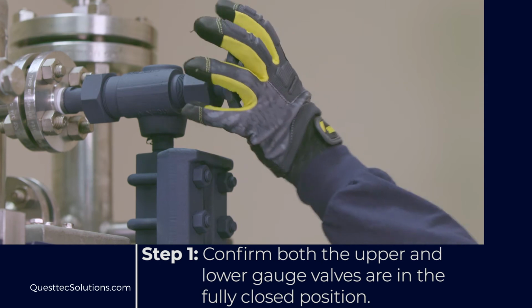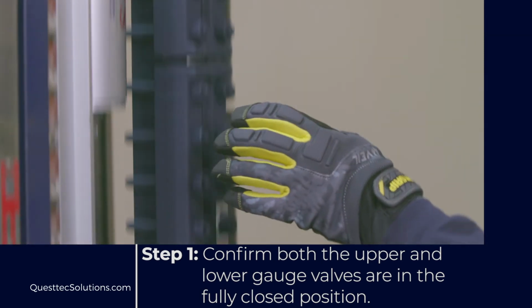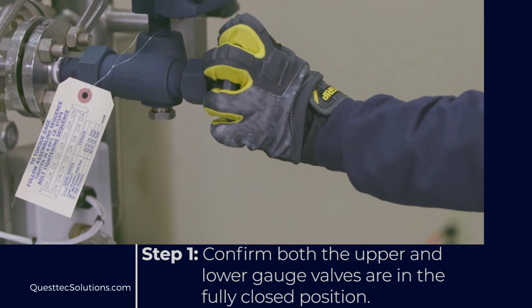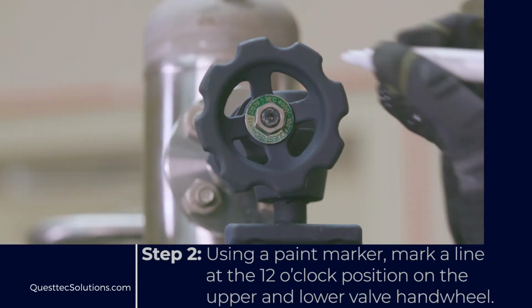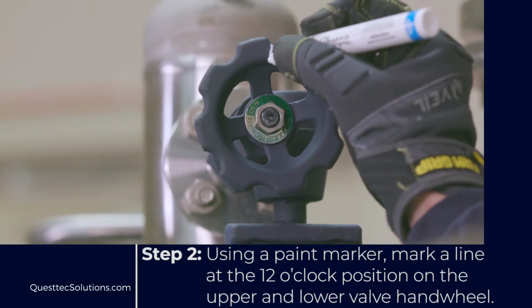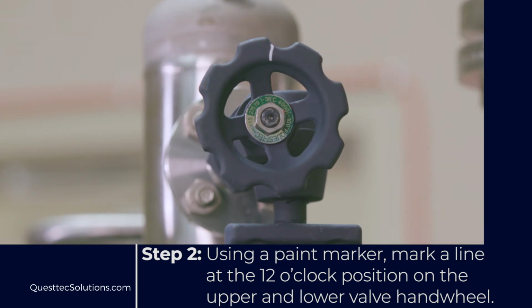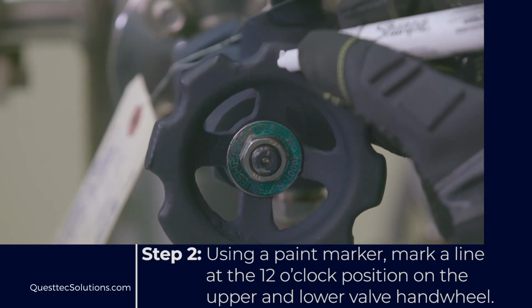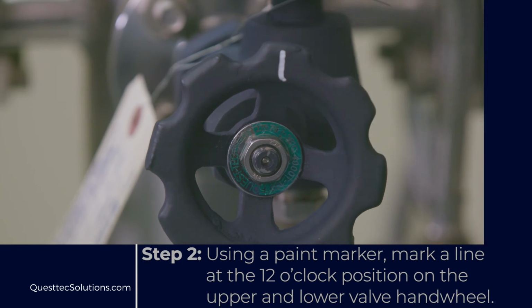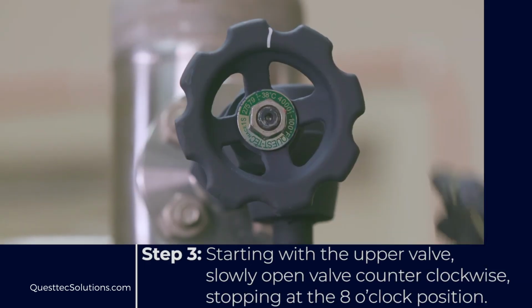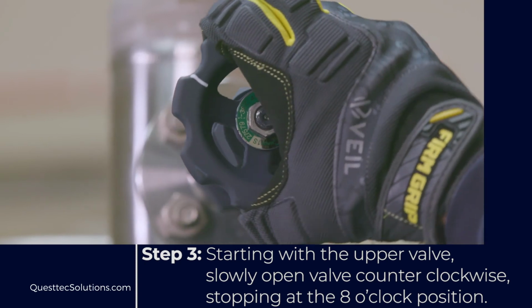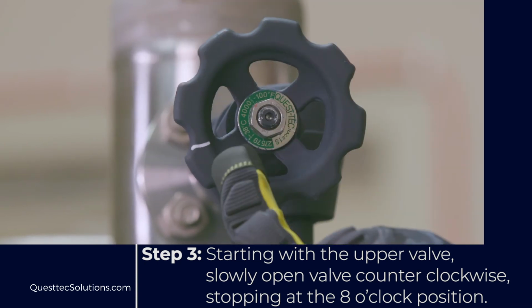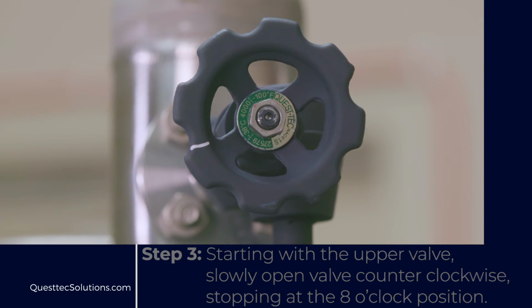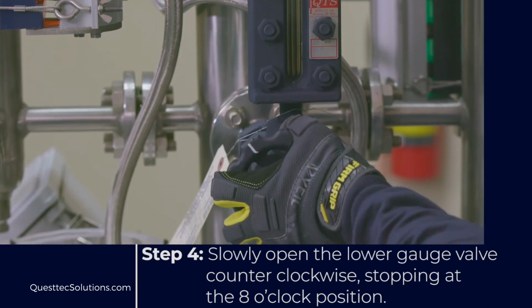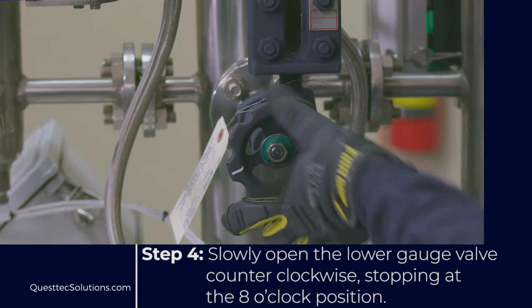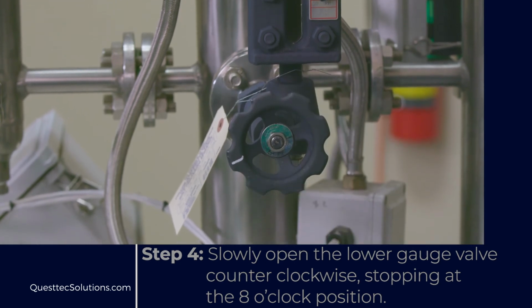Step 1. Confirm both the upper and lower gauge valves are in the fully closed position. Step 2. Using a paint marker with a contrasting color, mark a line at the 12 o'clock position on the upper and lower valve handwheel. Step 3. Starting with the upper valve, slowly open the valve counterclockwise, stopping at the 8 o'clock position. Step 4. Slowly open the lower gauge valve counterclockwise, stopping at the 8 o'clock position.